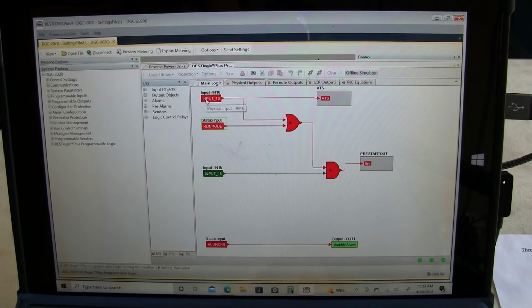Same thing with input 16, which is a remote start. See, it lights this up and gives our pre-start out, so it activates that heater. So now if we turn input 15 off and hit run mode, we don't get a pre-start, we just enter run mode. Same thing with input 16. I'm just double clicking on these to activate them. See, we don't get our pre-start, we just start the genset up remotely.